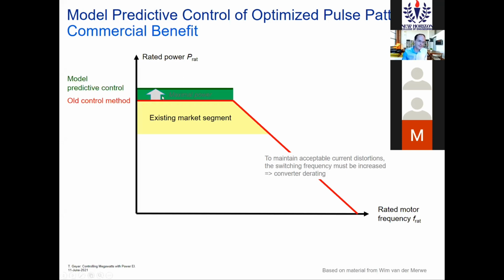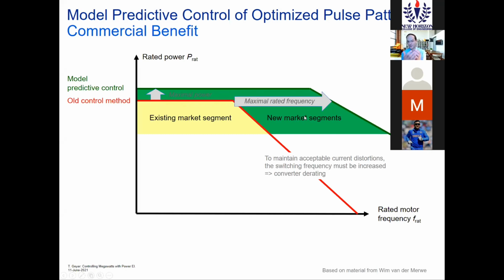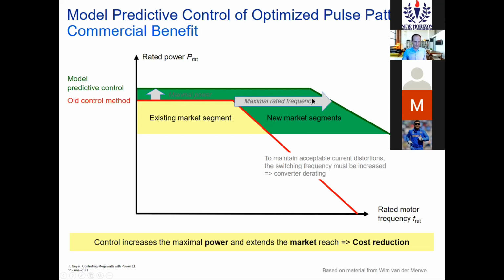Now with MP3C, we can reduce the current ripple. So that means we can increase the current. We reduce the switching frequency, so we can increase the current, and we can increase the voltage a bit. So we get a few percent more power at low speeds. But this derating point happens much later because we can achieve the same harmonic distortions at a lower switching frequency. So the derating kicks in much later. And the green area is effectively money, if you want. So you get more money for the same hardware, which is nice here, but it really pays out at these higher fundamental frequencies. So there's a nice cost reduction to be achieved.